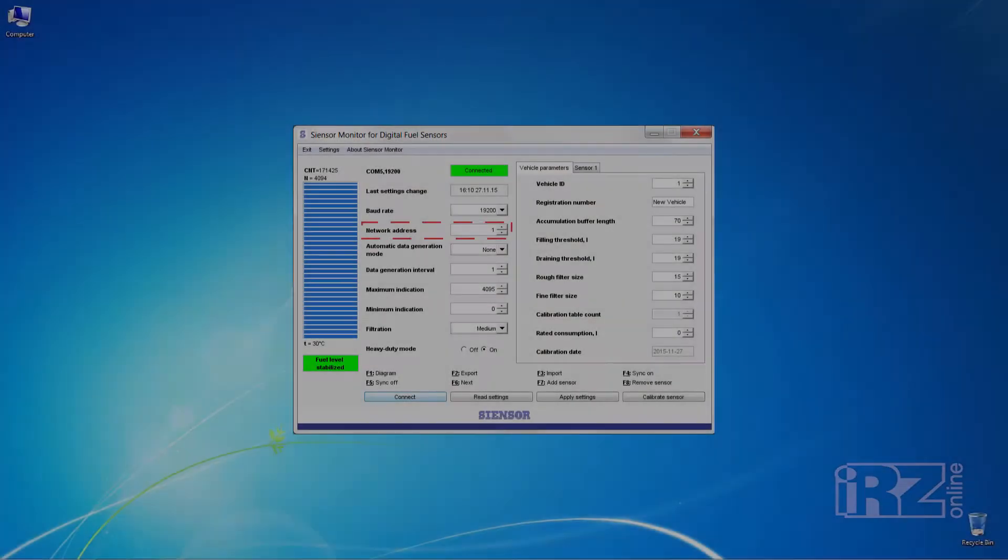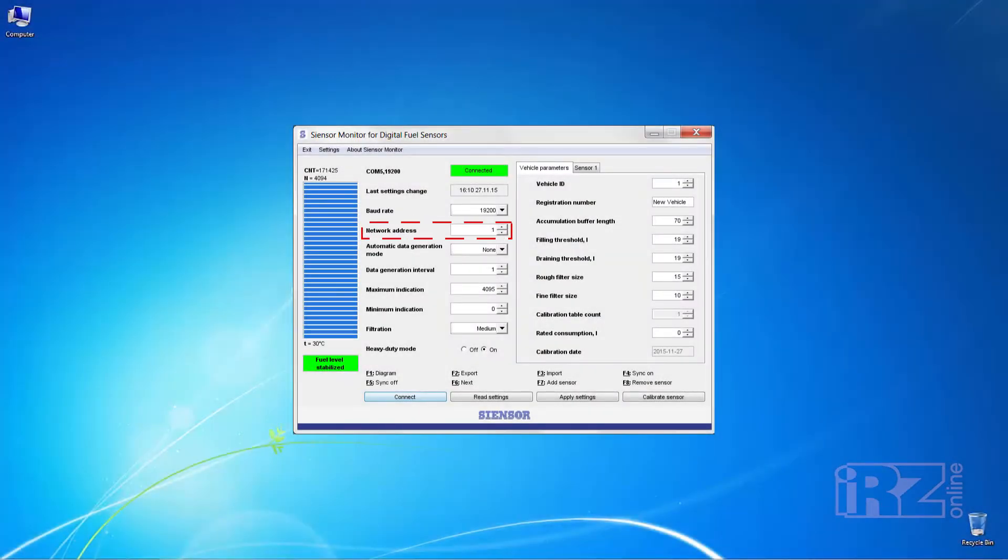If the terminal is connected with only one sensor, put one in the main window in the program field network address. If there are some sensors, then every sensor should have a unique network address. In the mode no distribution, sensor outputs data requested by the terminal. In the binary and character mode, data is transmitted automatically by a specified interval, which can be configured in the field below. If required, you can change the discretization by setting its minimum and maximum value.